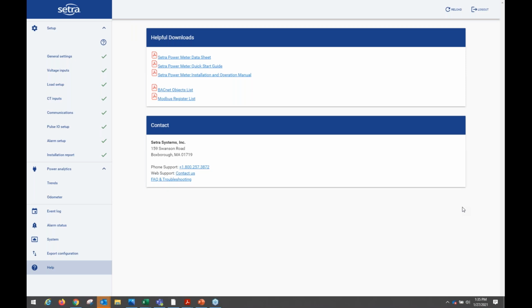Tom, are fuses built into the voltage feed local to the meter, or would external fuses be required? That all depends on the specification, as external ones may be required for that locality. But we do have a 200 KAIC fuse in the voltage path to protect the meter from any surges. Usually something else will blow much before that fuse will blow to protect the meter. So I won't say you never need them, because certain times they're part of a spec and someone demands that they're there for fuse leads, but for the most part, our meter does not require them as long as you have a disconnect breaker.